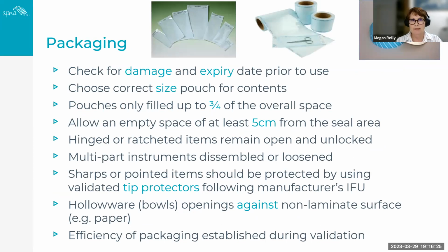So we need to be using validated packaging materials, and materials that will permit the removal of air from the pack, allow for the penetration of the steam into the pack, and then the removal of the sterilising agent and any water vapour that might be left behind. So it's really important with your packaging, whether you're using self-seal pouches or laminated roll or you're wrapping, that you check for any damage. You check the expiry date prior to use as well. So don't decant your self-seal pouches, for example, from the box that they come in, because often it's the box that actually has the expiry date on.